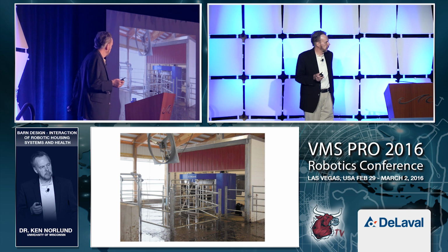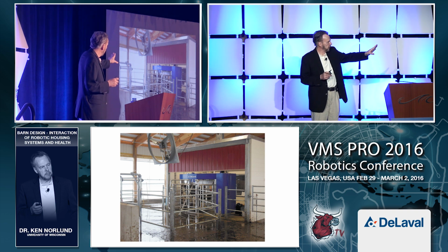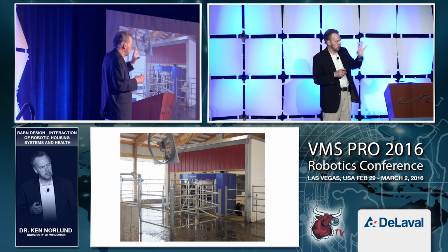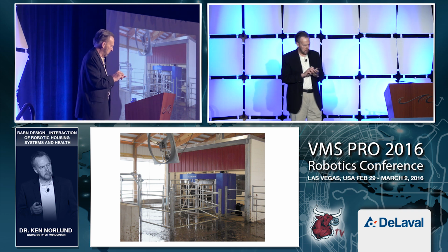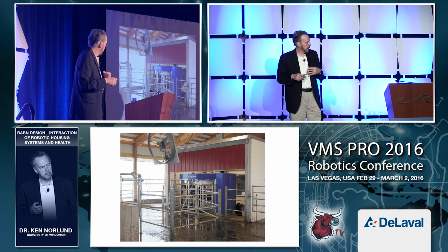So here's a robot, and again, you see the solid sides, 3 sides of it, opening on this side. Here the fan has been installed to blow air away, but there's quite a bit of science worked out as to where air is drawn into a fan, and you'll be as likely to draw air from right below the fan up and around as you are from over here. And I guarantee you there's nothing coming out of that.